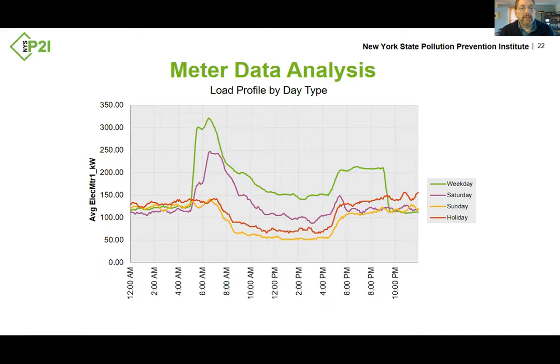So what we found here was that as the main shift comes in and fires up all of the equipment for production, there's a really big spike, and they pay a terrific demand charge from that. So what we were able to do is convince them to split up their shifts so people come in at staggered intervals, and the equipment that they start up then spreads out over a wider period of time, but a lower peak. So that saved the company about $14,000 a year in demand charges when they were able to implement that.